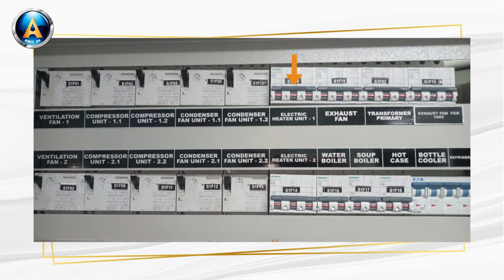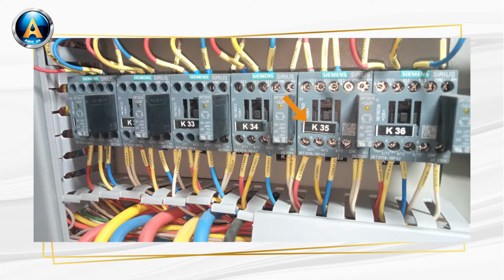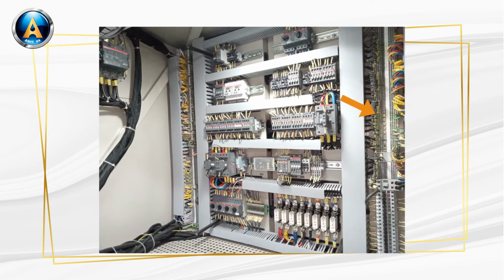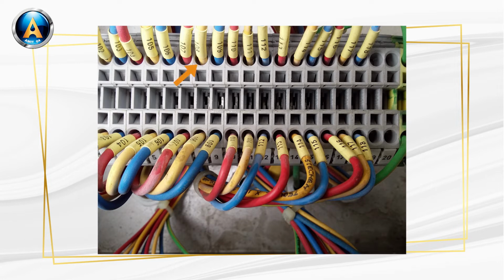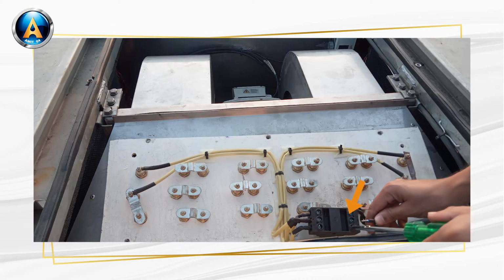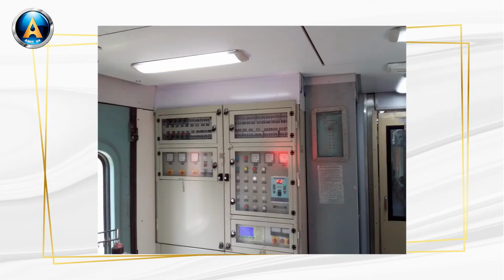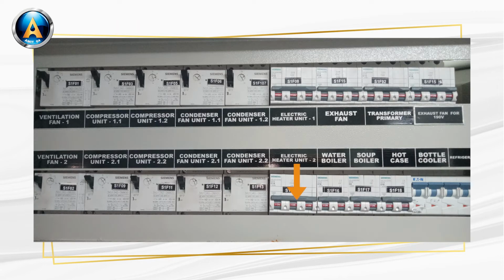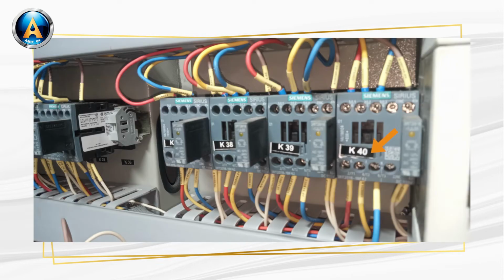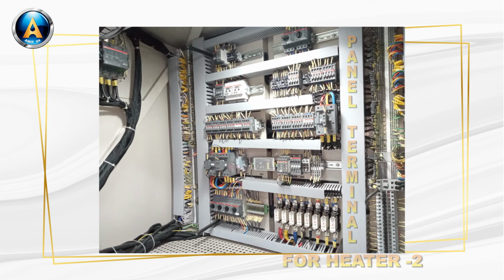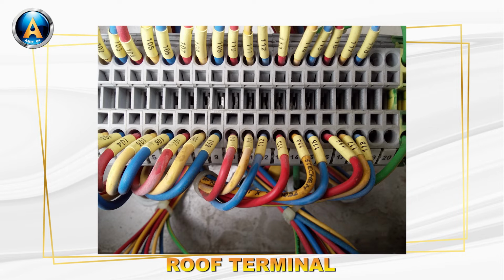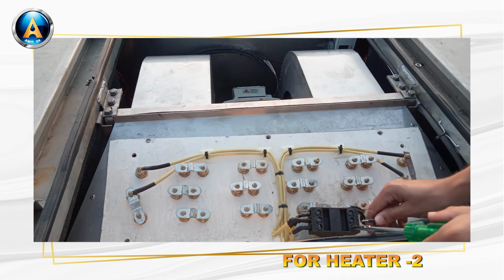This is heater 1 MCB, K35 contactor. This is a 415 volt AC panel terminal, and this is a 415 volt AC roof terminal, and this is an excess temperature protector device at the non-power plant end heater unit. This is heater 2 MCB, K40 contactor, and this is the excess temperature protector device at the power plant end heater unit.